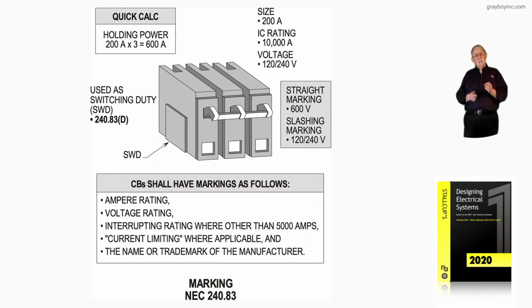So that's why sometimes fuses are used mainly with motor loads and other types of loads that require inrush values to start, run, and operate the load and so forth. Now, the size, it's a 200 amp. The interrupting rating is 10,000 amps. And the voltage on it is a slash mark voltage, 120, 240, as you see in the illustration.